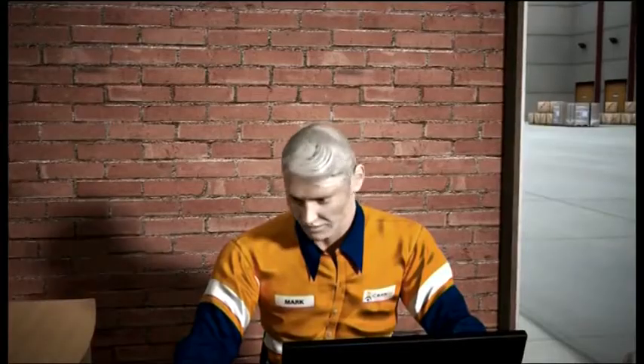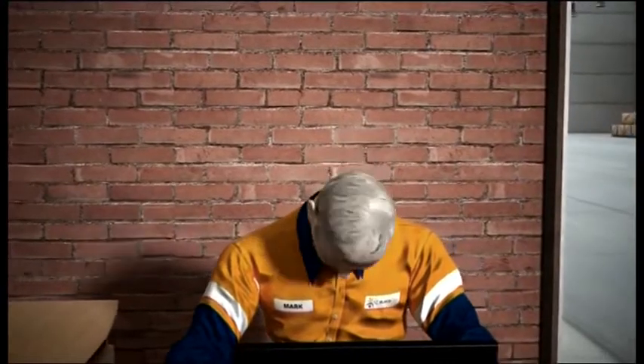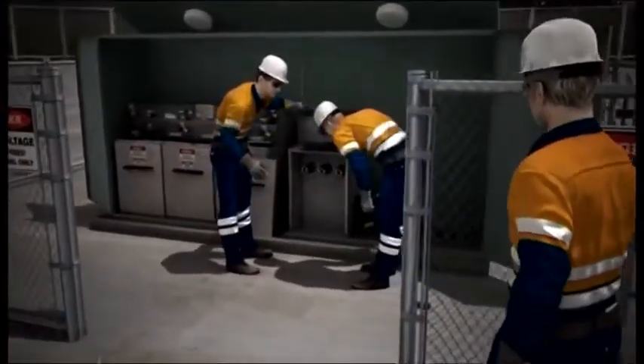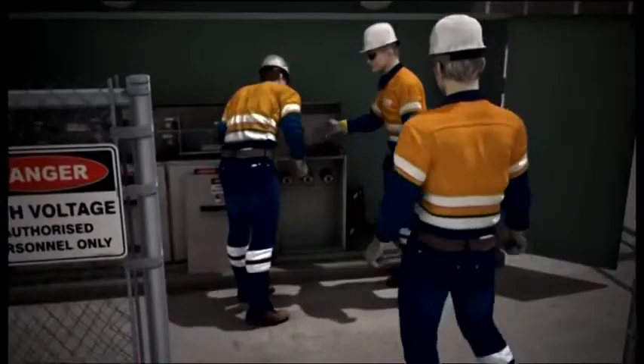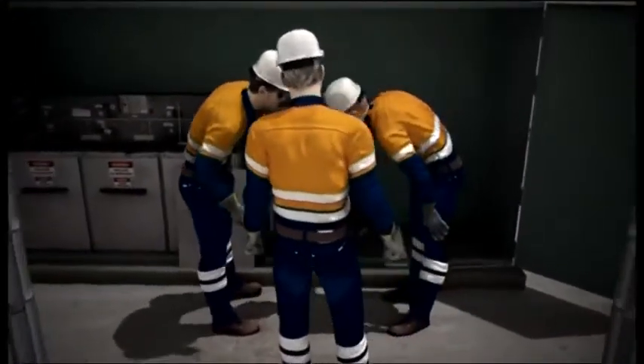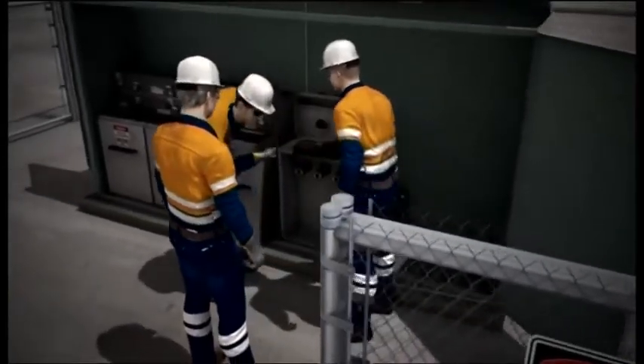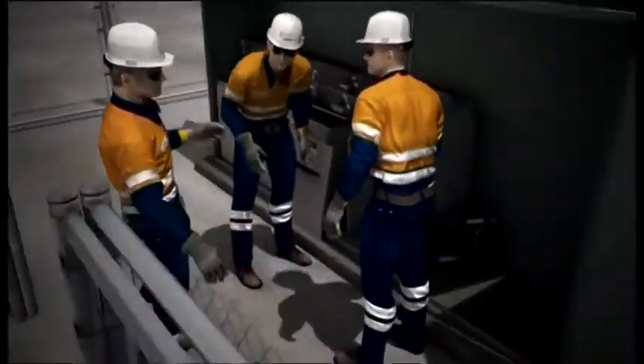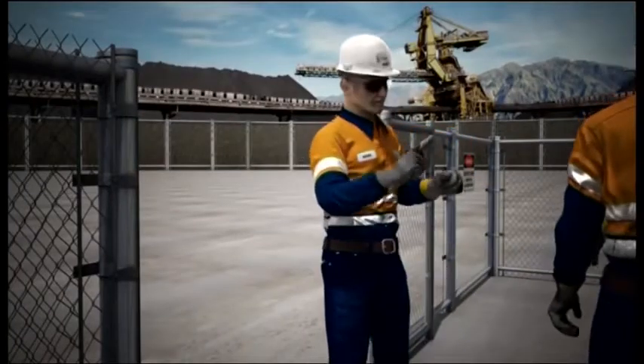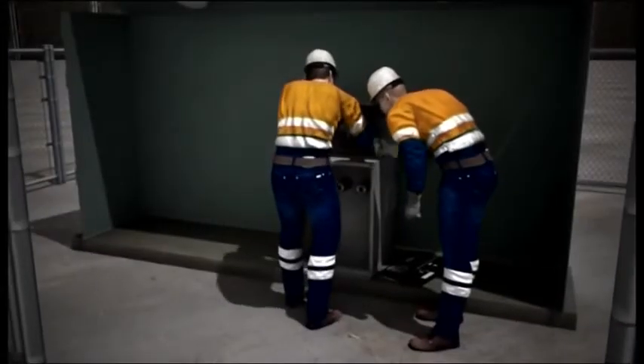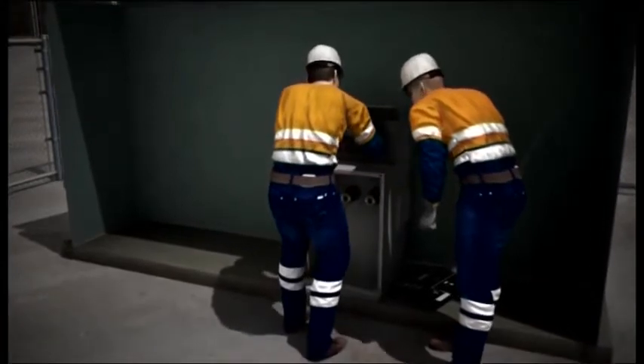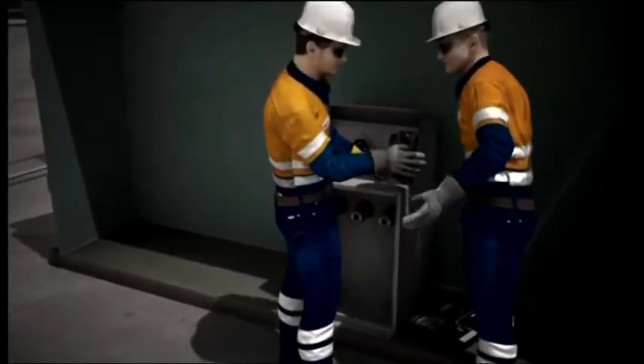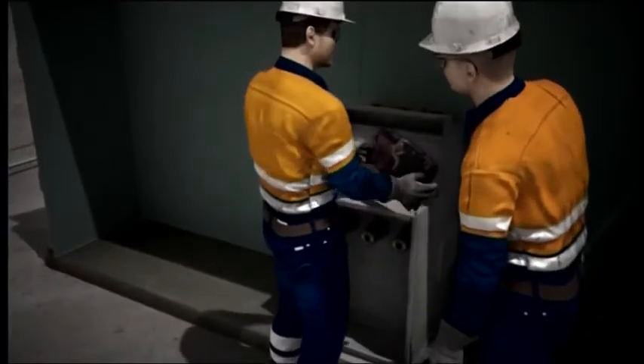Attempts to find a manual on the internet and telephoning the manufacturer's agents are also unsuccessful. By the time the supervisor returns, Dave and Andrew have successfully removed the faulty mechanism. They inspect the mechanism and discover that it has a broken spring and is too badly damaged to be repaired. The supervisor instructs them to remove an identical switch mechanism from a spare unit at a nearby distribution point. However, in removing this spare mechanism, the actuating springs inside the unit lost tension, making the switch unusable as a replacement. Every effort to recompress the springs in the workshop was unsuccessful.